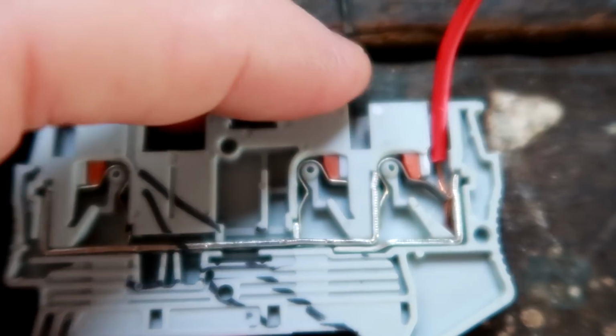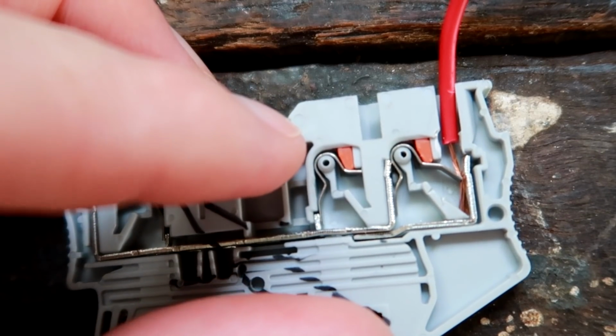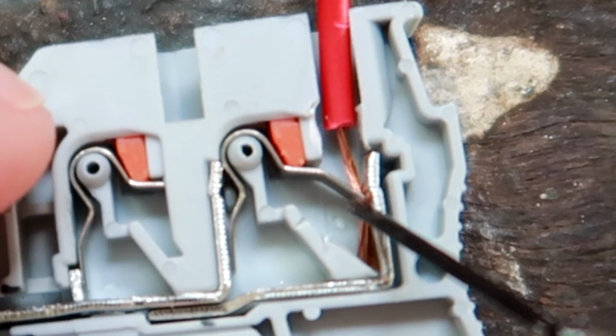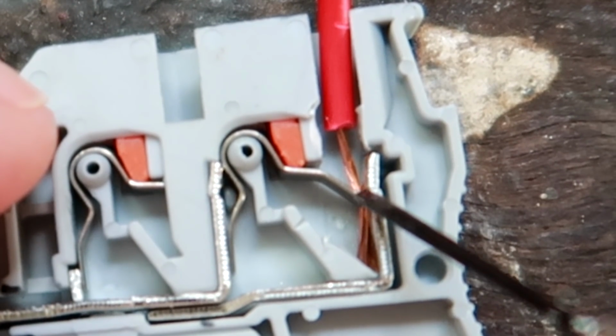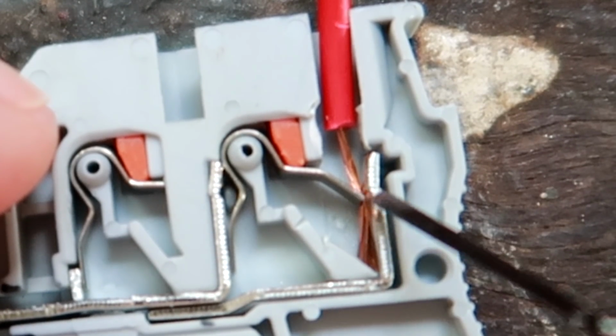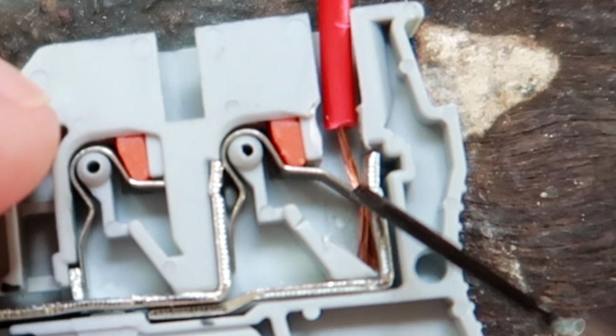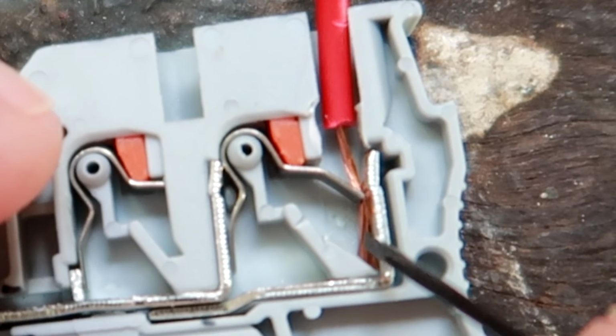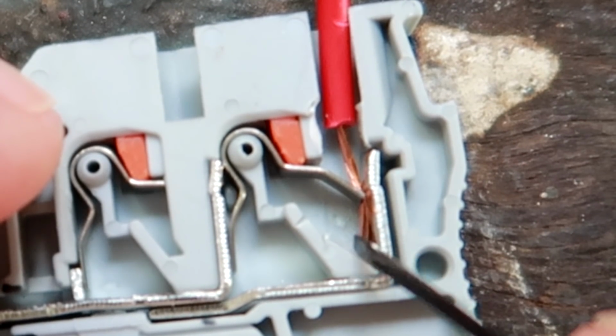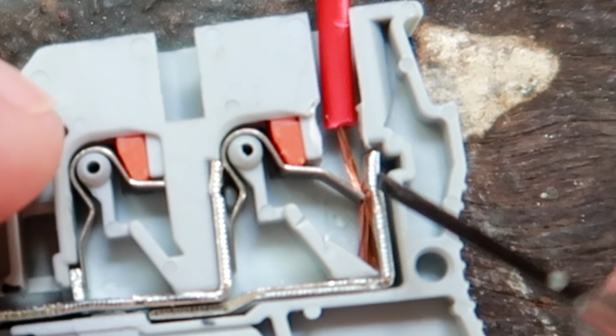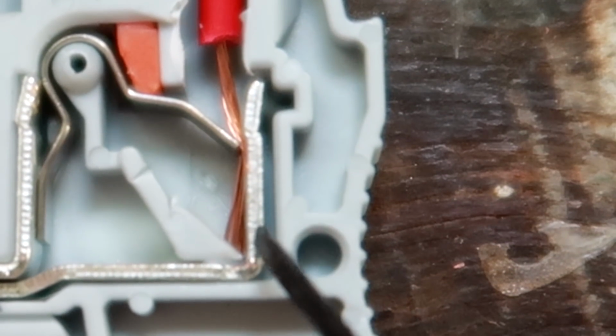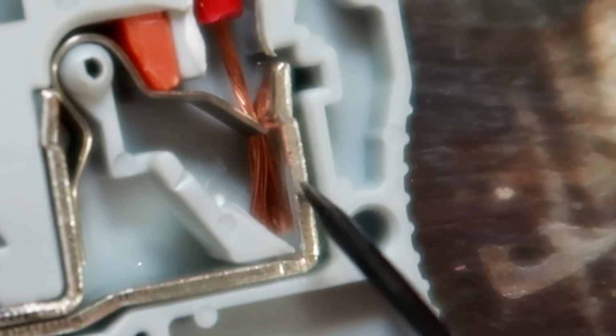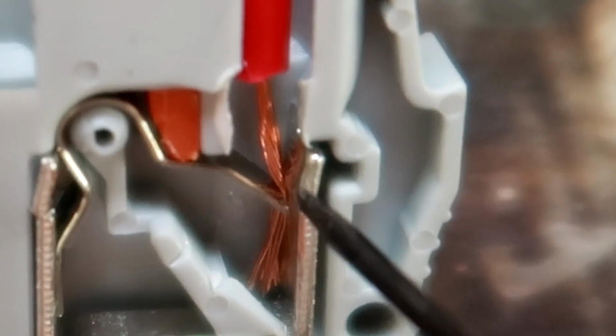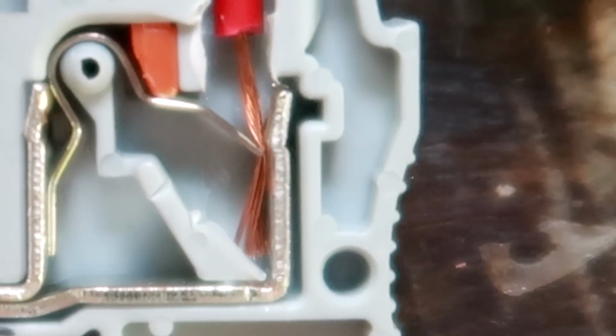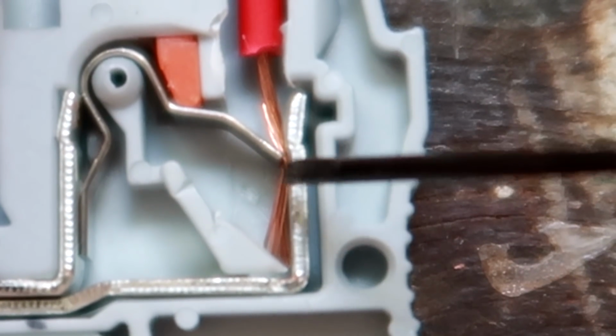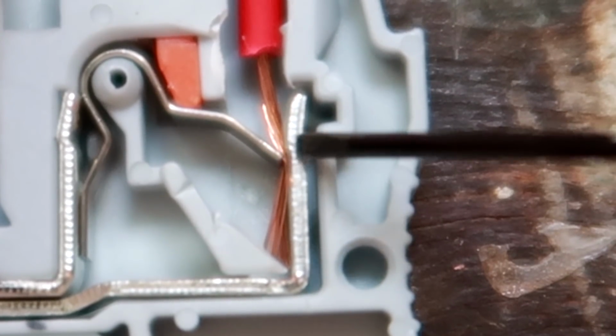And here you can see what I think is a bit of a problem. The spring here pinches the cable only at one location, pressing it against the bus bar just where they touch. You can see the bottom of the cable actually bends away from the bus bar, and so does the top. This is how it looks inside the terminal - there's only one connection point between the cable and the bus bar here.